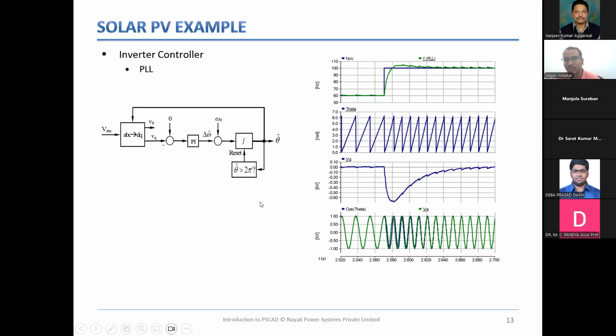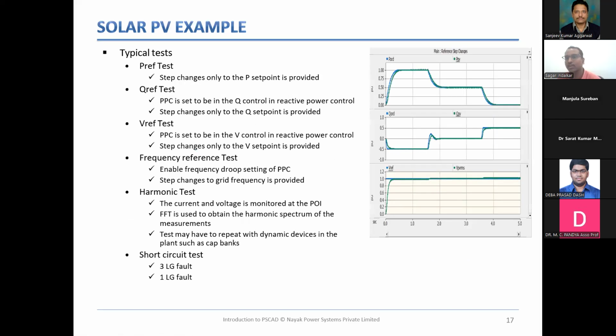You perform a study, and that study typically involves certain tests, to check whether your plant follows the grid code or not. Typically that test involves set point changes. For example, you will put the PPC into active power control mode, and you will give the PPC certain set points. Now, typically that set point is performed at every 10% of the operating range. So between 0 to 100% P, you will give a set point to the PPC.